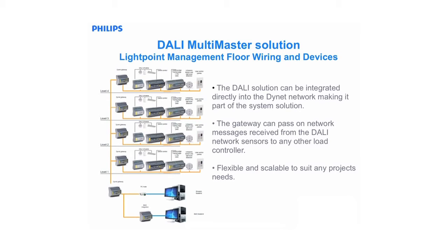By having the DALI MultiMaster system within the Dynet network, we can receive messages from a DALI sensor and have that transmitted to any other device on the network. For example, the DUS804C DALI sensor may need to instruct another controller, such as a relay or LED dimmer, that it has detected presence within an area. This is possible with the Dynet network, so multiple devices are able to respond to the DALI messages. Other network devices, such as an ultrasonic sensor, user control panel, or even a timer clock, can send out a message to the Dynet network, and the DBC120 DALI will respond to the message appropriately.